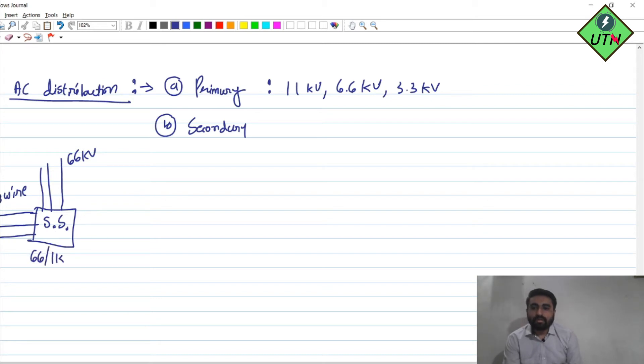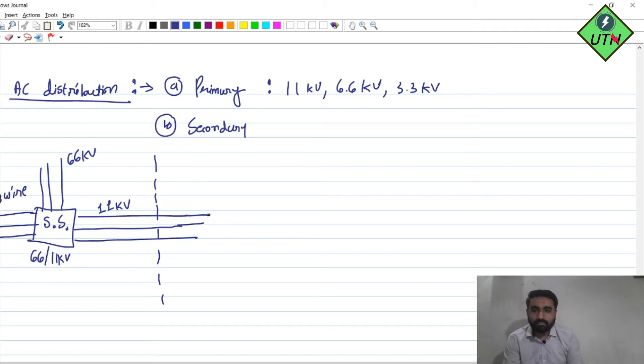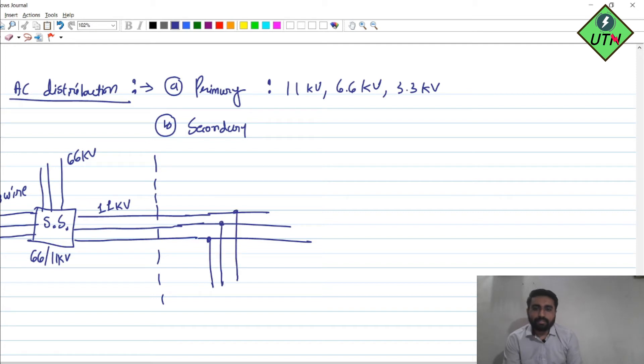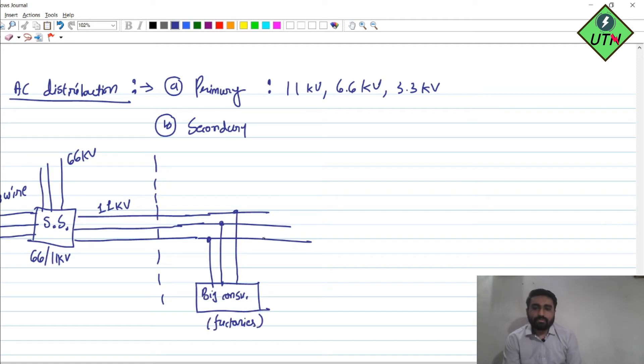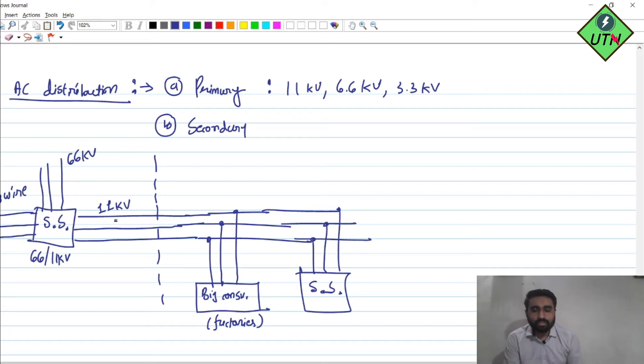At the substation, voltage is stepped down from 66 kV to 11 kV. So here at the distribution level we mostly work at 11 kV. In the primary distribution system we may have large conductors supplying large industries that need 11 kV, big factories, and different substations also connected at 11 kV, 6.6 kV, or 3.3 kV. The mostly used voltage for primary AC distribution is 11 kV, using a 3-phase 3-wire scheme.